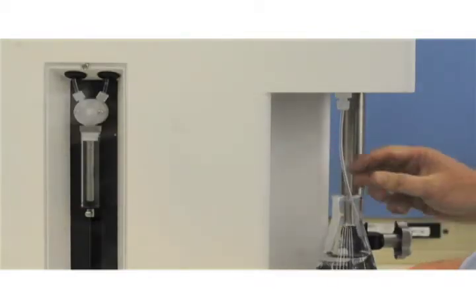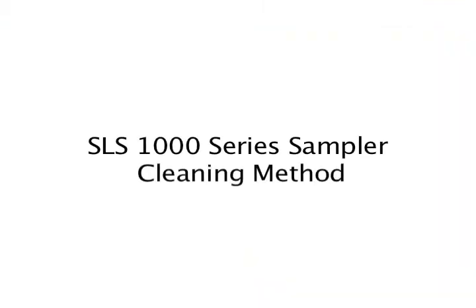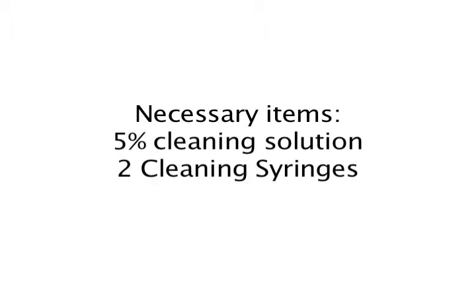Even after following good sample practices, occasional optical cleaning will be required. The SLS 1000 series sampler has been designed to allow the operator to perform this process using two methods. The first method is simple to accomplish and does not require removing any of the instrument covers. We recommend using this method first since it will resolve most contamination issues.